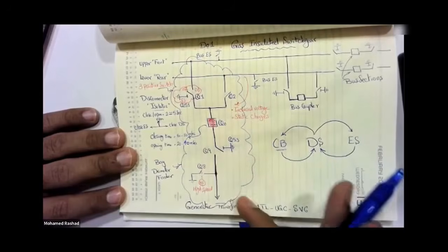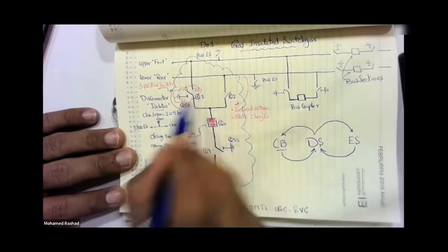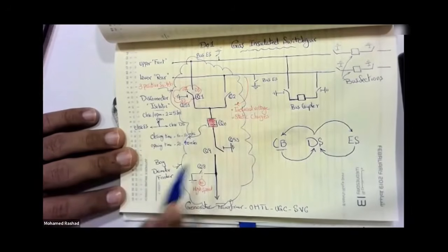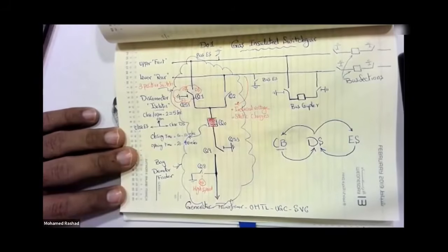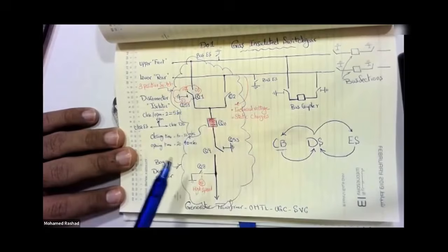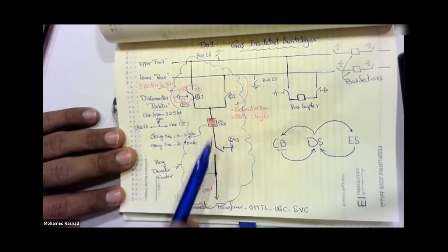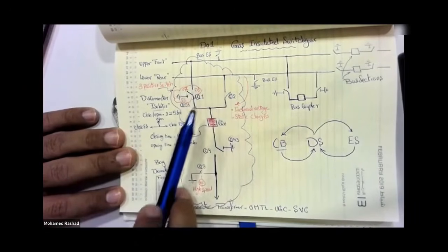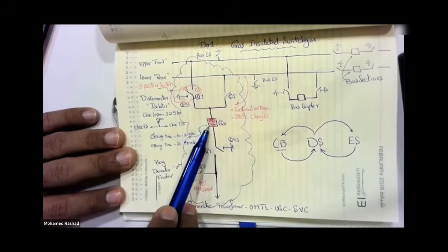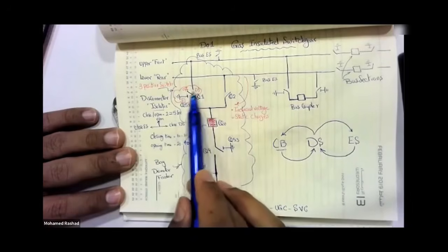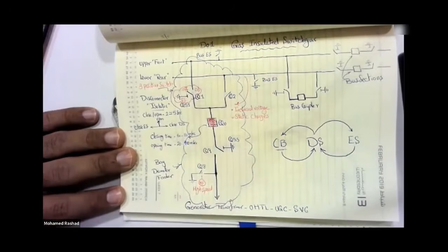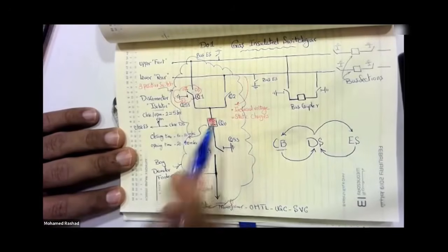All right, so now, as we agreed to know the breaker, Q1 or Q2 must be closed. And Q9 must be what? It must be closed. All right, that's great. So these must be closed first. Why must these be closed first? Because if you close a breaker, none of these will work to close, as they are not designed to close or open for loads. Only the breaker closes and opens for what? For loads. So we close Q1, for example, and Q9, then finally, who do we close? We close the breaker.